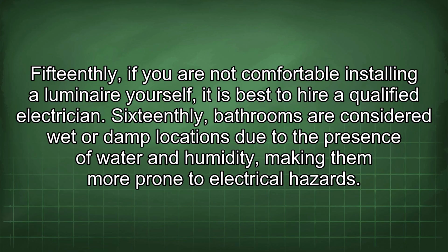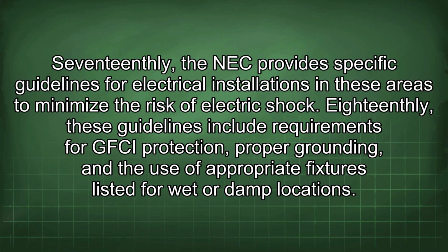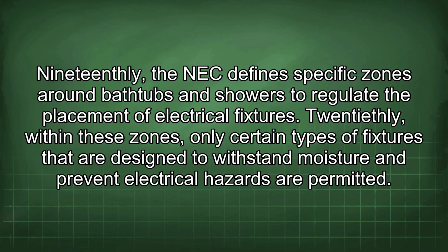16thly, bathrooms are considered wet or damp locations due to the presence of water and humidity, making them more prone to electrical hazards. 17thly, the NEC provides specific guidelines for electrical installations in these areas to minimize the risk of electric shock. 18thly, these guidelines include requirements for GFCI protection, proper grounding, and the use of appropriate fixtures listed for wet or damp locations. 19thly, the NEC defines specific zones around bathtubs and showers to regulate the placement of electrical fixtures. 20thly, within these zones, only certain types of fixtures that are designed to withstand moisture and prevent electrical hazards are permitted.